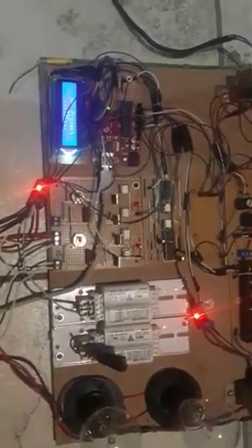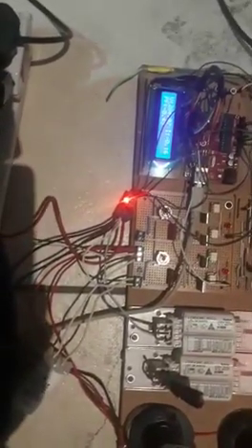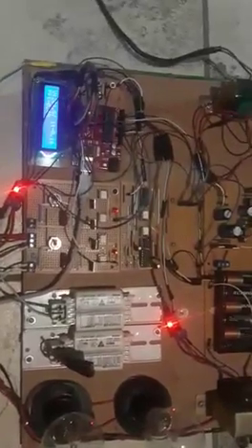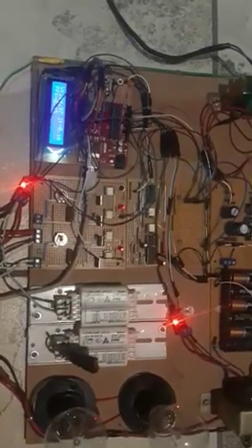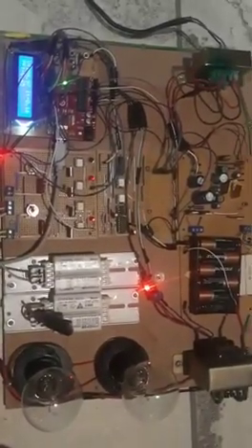In my case, I'm using a 220 supply from a normal plug, and it's also to try and improve the power factor and make it close to unity by also ensuring that the amount of current drawn from the network is minimum. This can save in industrial application because companies are penalized for poor power factor because they reduce the carrying capacity of conductors, transformers, even generators. They create strain on them.